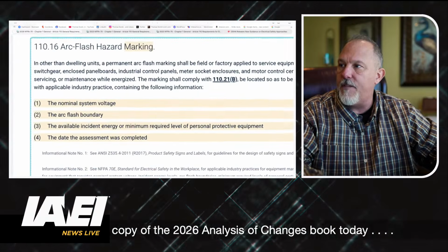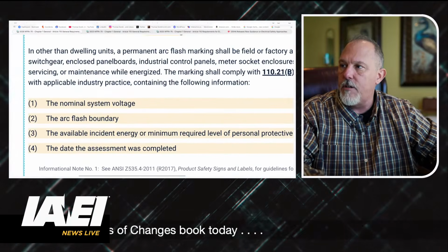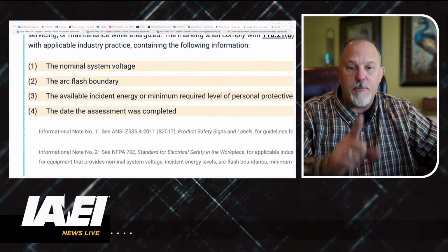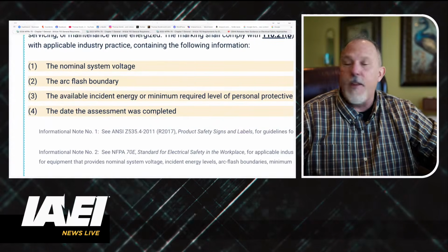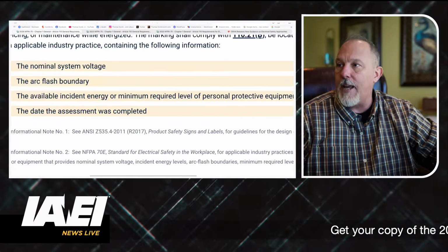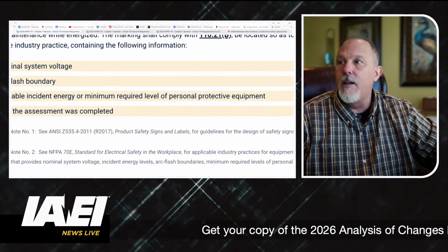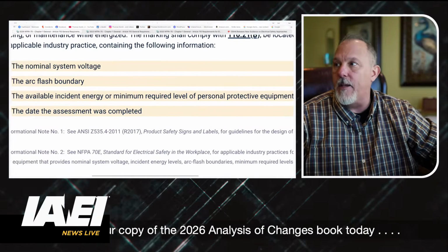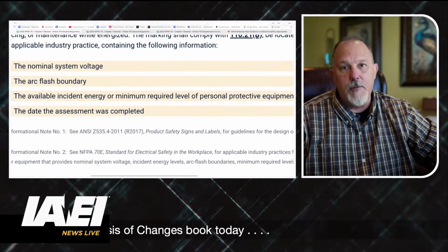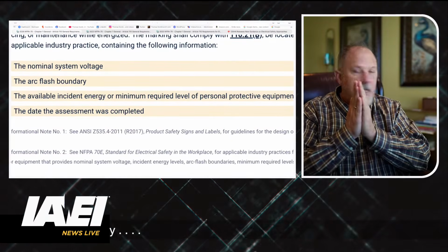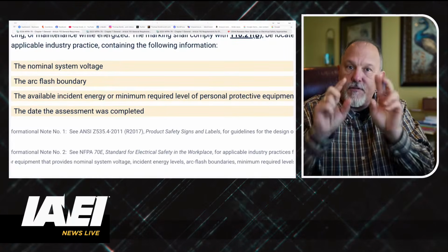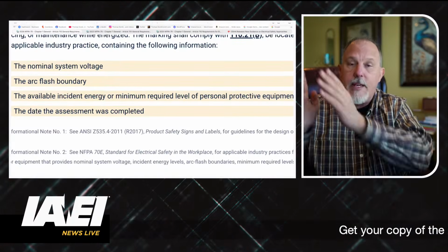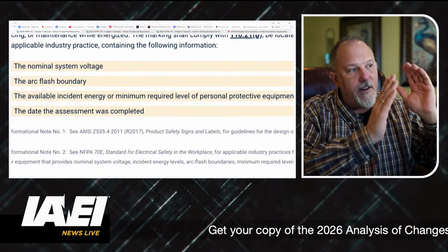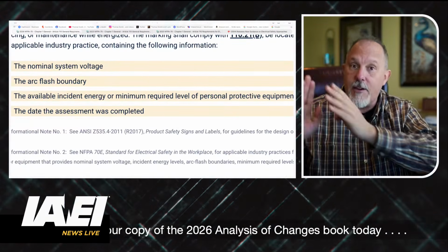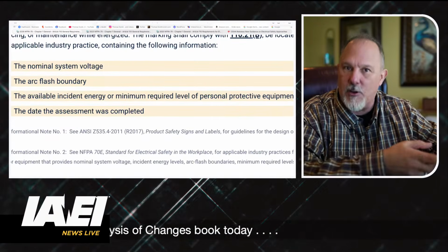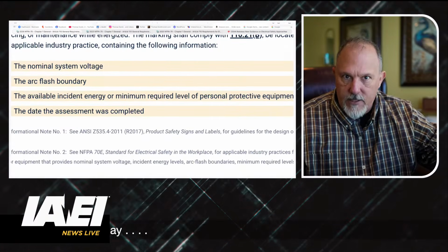Here you have to have the nominal system voltage, the arc flash boundary, and then the third one has to be the available incident energy or minimum required level of personal protective equipment. Now, that item 3 is your NFPA 70E. You have two options in 70E: the calculation method and the PPE category method. Never shall the two mix.